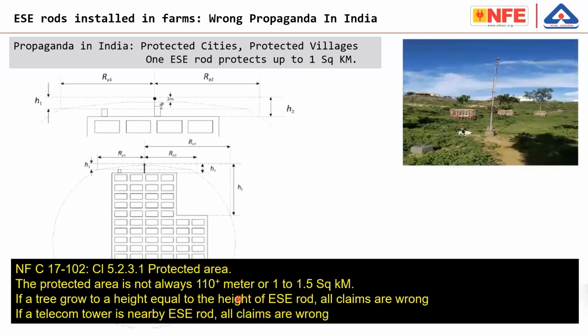Even if you read the NFC standard, the protected volume, depending on the level of protection, is sometimes only 20 or 30 meters, even applying the formula. Anyway, those formulas are not applicable or accepted anywhere. If a tree grows above the height of the ESE rod, the claims are totally wrong because the lightning will go to the tree. Imagine in 2020 you install a rod costing 50,000, 75,000, or even a lakh of rupees, and after 1 year a nearby tree is taller than it—then the claim itself is wrong as per the standard. The claim in the standard itself is wrong. That is the point.